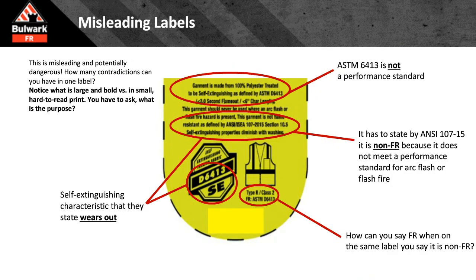This is some of the nonsense you will see out there. Here it says it meets 6413 and self-extinguishes. What does that matter? You can't use it in an arc flash or a flash fire because ANSI told you 6413 is not one of the standards allowed to claim flame-resistant properties. So this particular label tells you it's not flame-resistant. Then on the same label, it tells you it is flame-resistant because it says Type R Class 2 FR. Then in the fine print, it states the self-extinguishing characteristics will wear out. So if this was rain gear, that's rain gear you can't get wet.